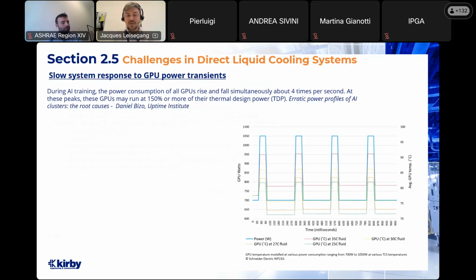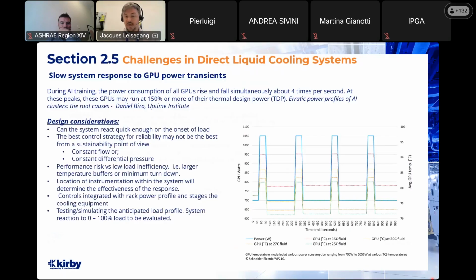clusters. So that shows us how quickly the load ramps up and down on these systems, and the fact that they're getting up to 150% or more of their thermal design power gives us an indication of what we're dealing with in terms of that thermal load. So when we're designing a liquid-cooled system, do we understand the thermal load profile of the servers that we're designing for? This coolant system, can the system react quick enough on the onset of load? When we're going from 0 load to 150% load, can our system react quick enough?